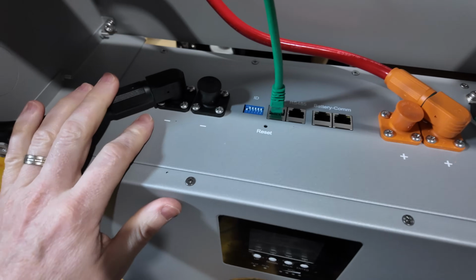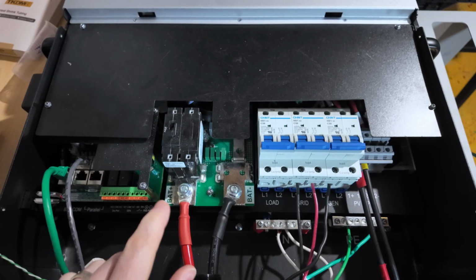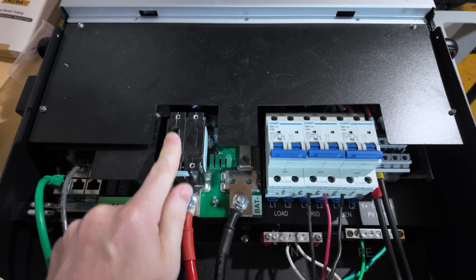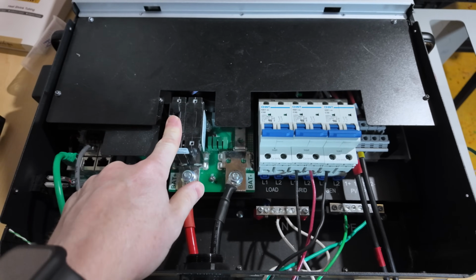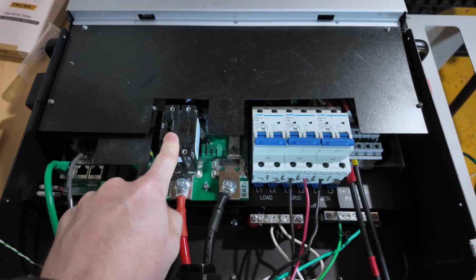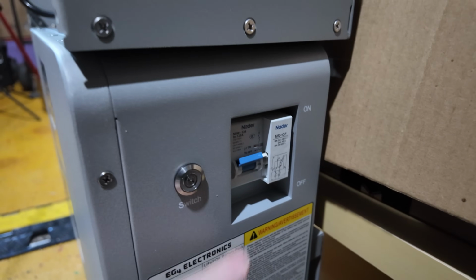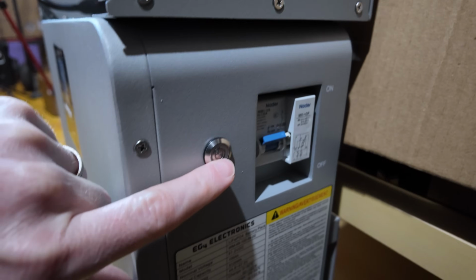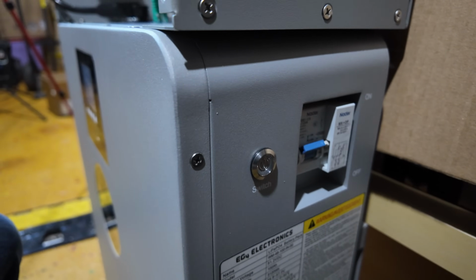So we've got everything connected up. Proper startup procedure is to close the breaker on the inverter first, turn it on. We'll then close the breaker on the battery, and then turn the BMS on.